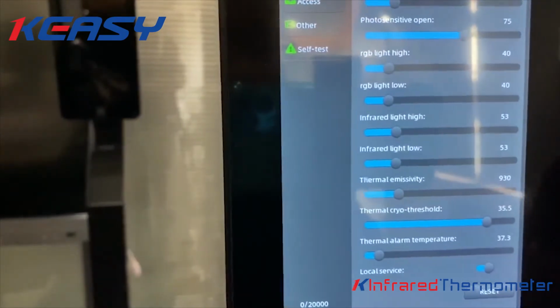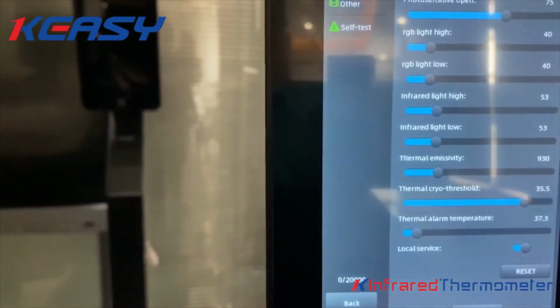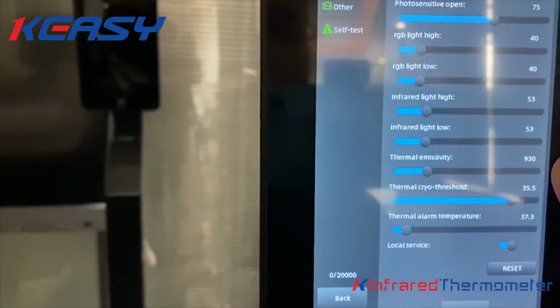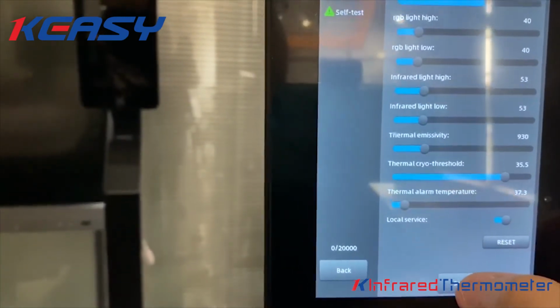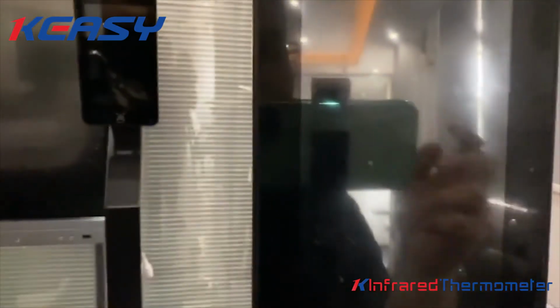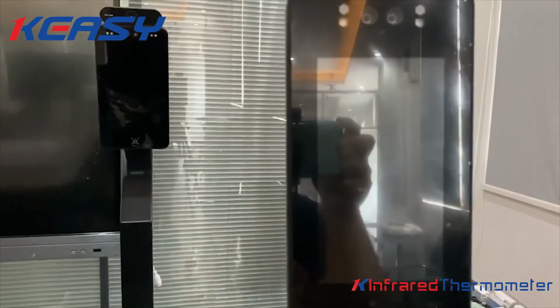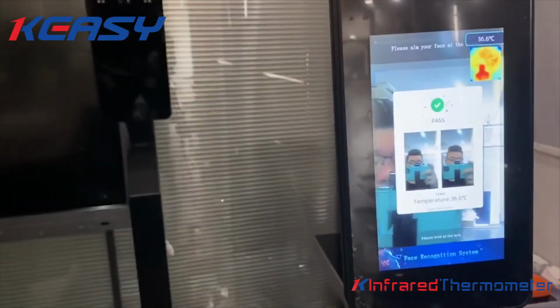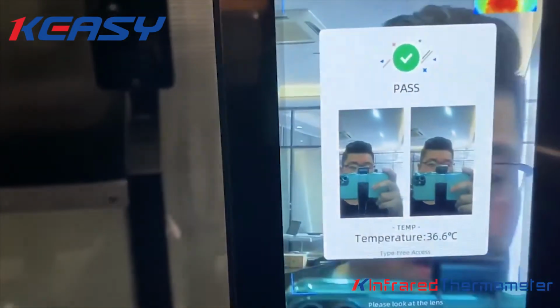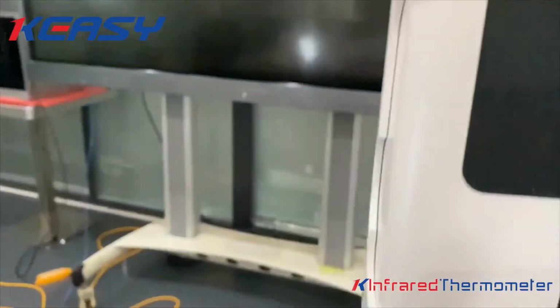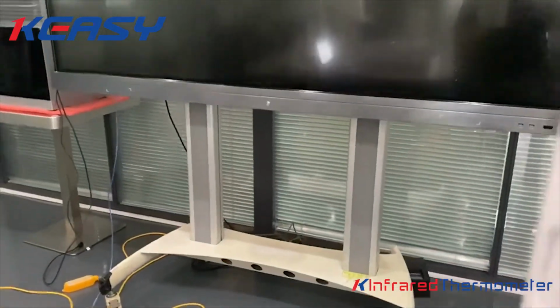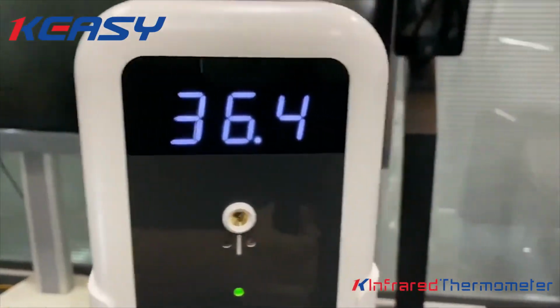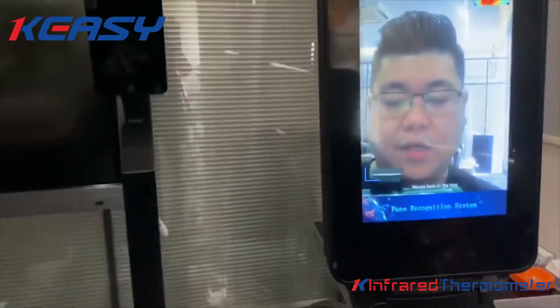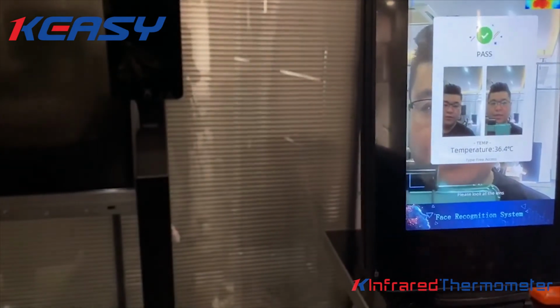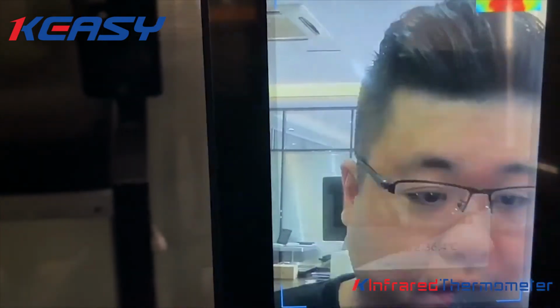The range of the emissivity we suggest is from 850 to 1000. So now we need to save and test again after power on. Okay, after power on again, now you will find that the temperature is already close to this thermometer. I will check again. 36.4, 36.5. So the accuracy is more or less 0.3 degrees. So now it is the same.